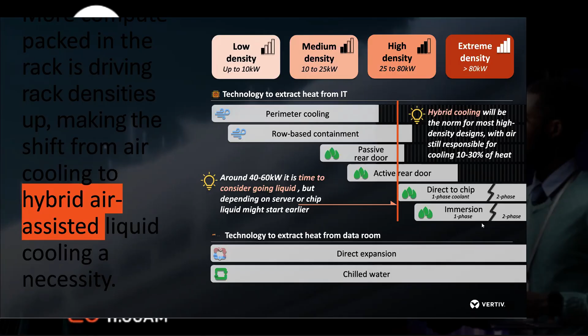So again, technologies to extract heat from data rooms could be direct expansion or chilled water. If you are going to do 10 kilowatts to 80 kilowatts, you can either choose direct expansion, which uses gas, or chilled water, which of course we're all familiar with, the big chillers we install in big data centers. As the heat increases, extreme heat requires direct-to-chip and immersion cooling, which we already looked at in the slides.